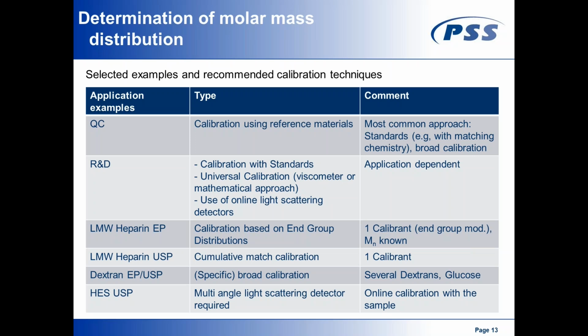It doesn't matter if your sample and your calibrants have different chemistry, you can always use this universal calibration curve. It will apply to all different chemistries. On the other hand, there's a so-called mathematical approach to that, which means if I do have Mark-Houwink coefficients for my calibrants and my sample, I can transfer calibration curves into each other.